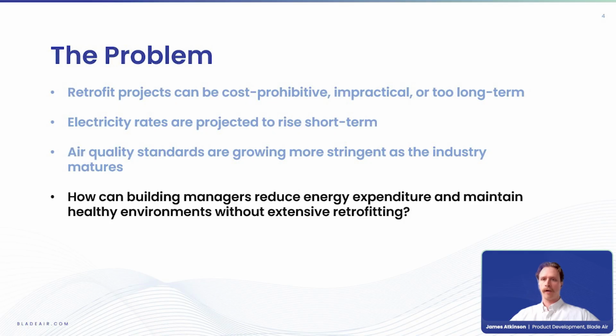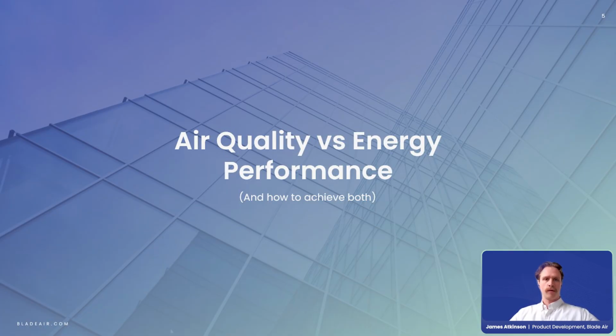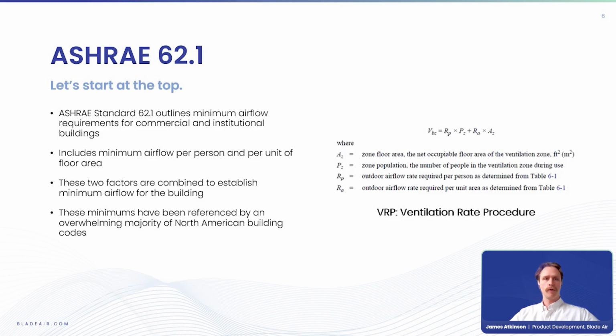The more data we learn, the better we characterize how indoor pollutants affect human health and productivity, and the standards themselves are also growing more stringent as we get more data. So we can't compromise on air quality, but we need to improve our energy performance. To address that problem, let's start at the beginning with how we actually design our ventilation requirements. I would assume that most of us are familiar with ASHRAE 62.1 and the residential standard 62.2, but just a quick introduction for those who aren't. This is a standard that outlines the minimum airflow requirements for commercial and institutional buildings, right? So banks, schools, any commercial or institutional project. This is really where the design airflow requirements will come from.